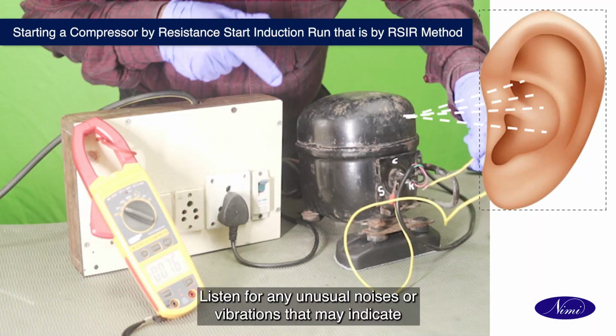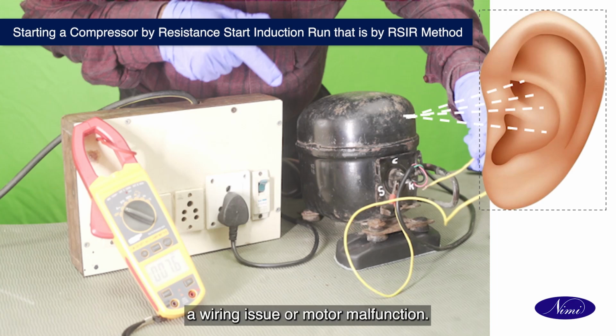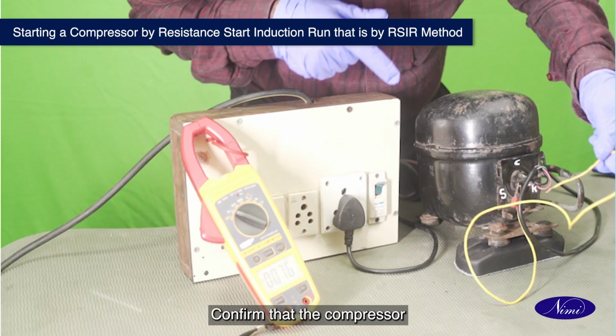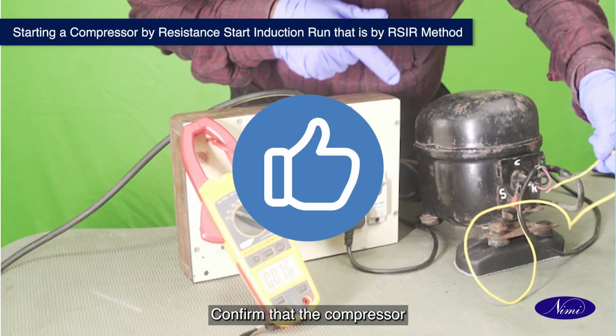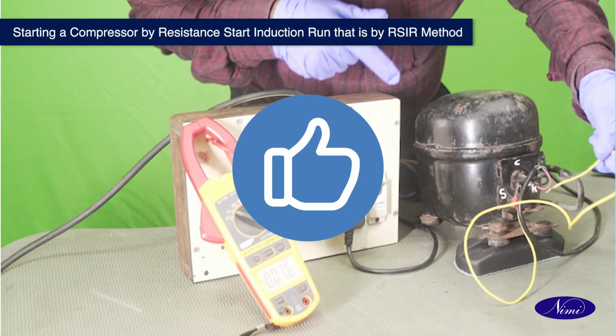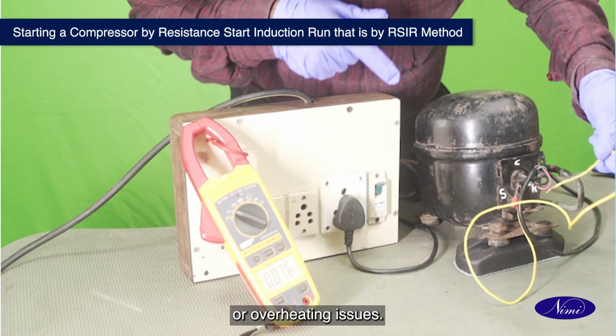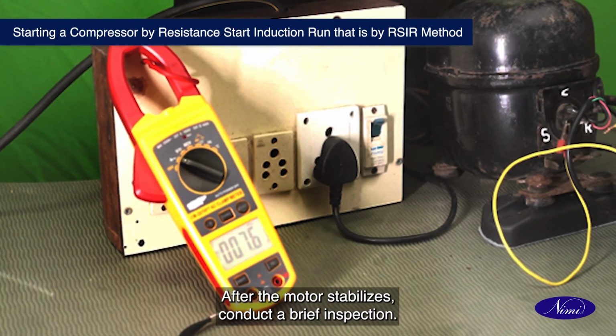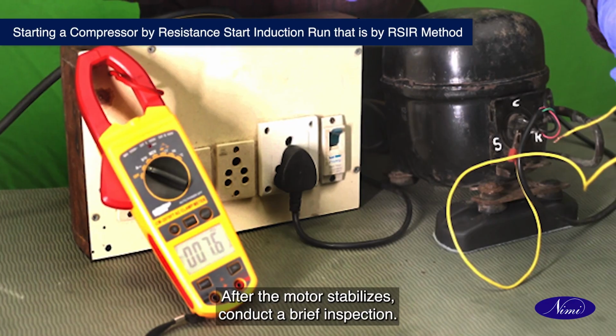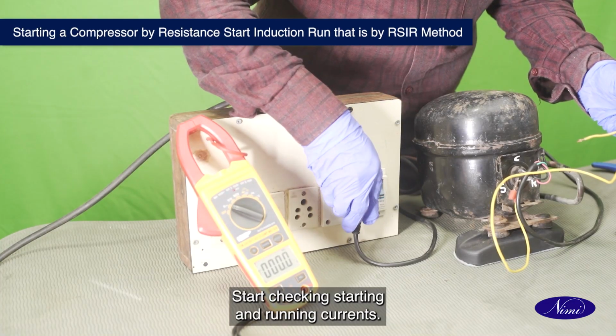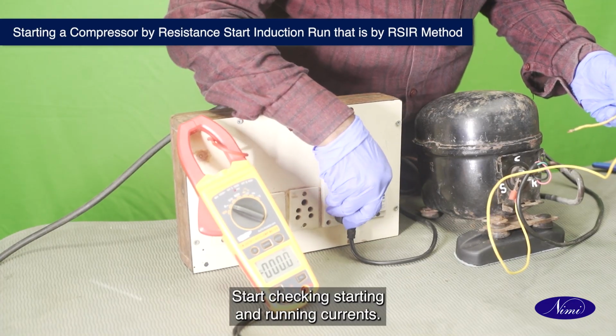Listen for any unusual noises or vibrations that may indicate a wiring issue or motor malfunction. Confirm that the compressor is running smoothly after startup. Ensure there are no abnormal sounds, excessive vibrations or overheating issues. After the motor stabilizes, conduct a brief inspection. Start checking starting and running currents.